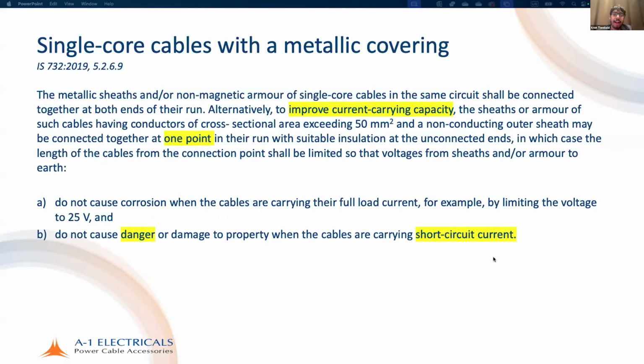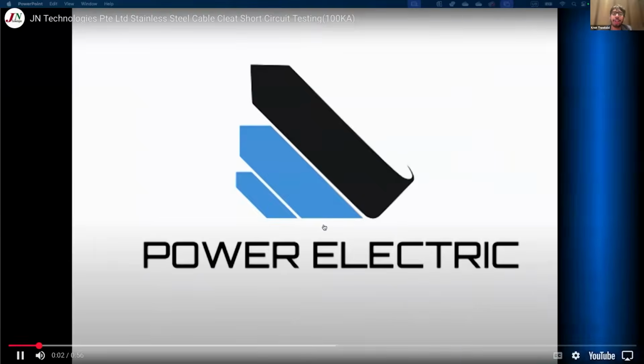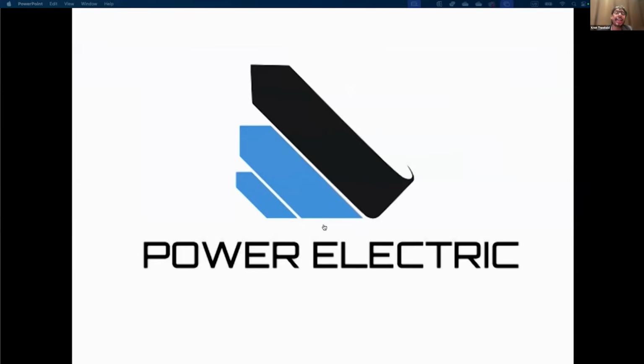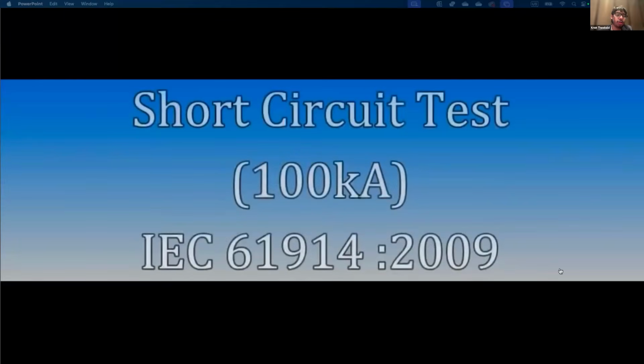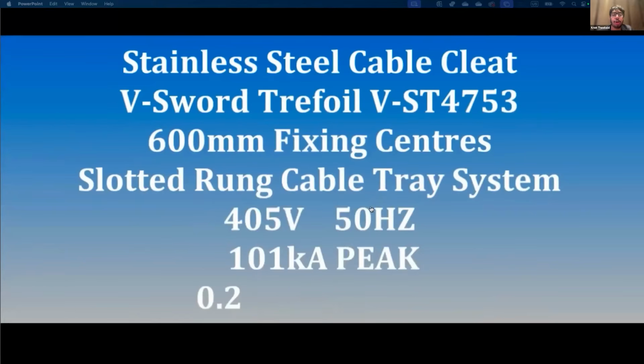Now, there are cleats that, according to the standard 61914, are designed to withstand only one short circuit, and cleats designed to withstand more than one short circuit. This is tested as per a certain process. This is just a video to show you how these are tested. So make sure that the cleats that you are purchasing are designed to withstand more than one short circuit. So yeah, see, this is how the short circuit tests are being performed. I believe Mr. Gandhi mentioned that the A1 product is suitable for much more than one short circuit, and as a classification according to the standard.